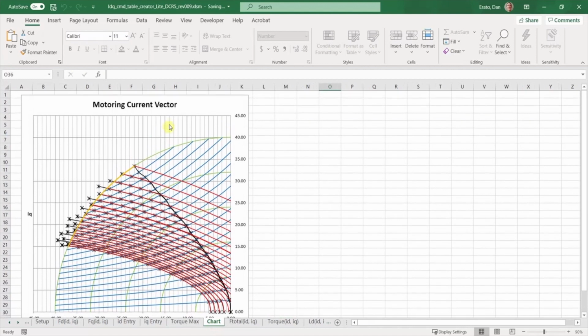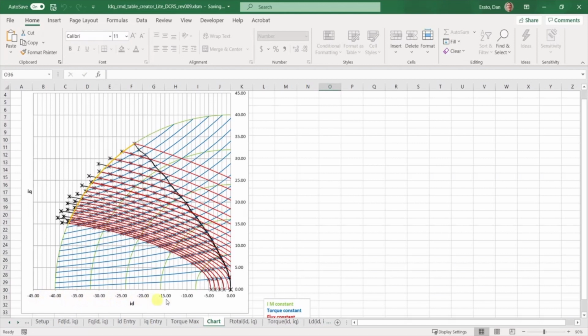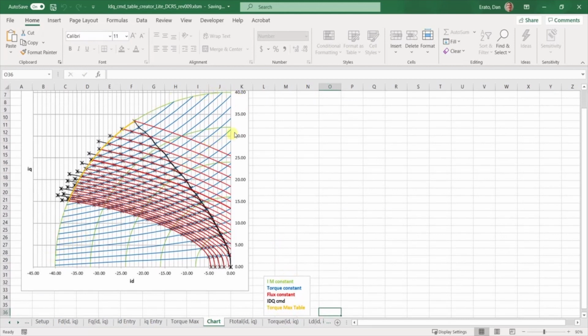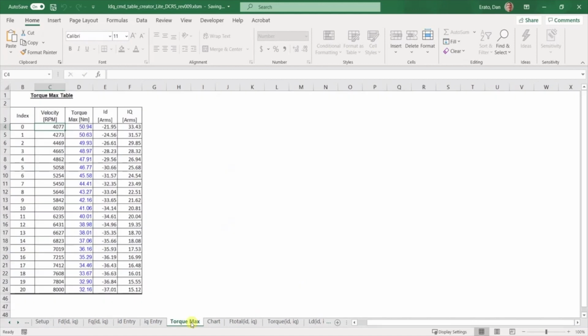The chart sheet graphically shows the IDQ command table with the current, torque, and flux constants. The green lines are the constant current curves. The blue lines are the constant torque curves. The red lines are the constant flux curves and represent the voltage constraints at higher speeds. The black line is the max torque per amp MTPA curve used by the drive below base velocity. At higher speeds, when the drive runs into voltage limits, the IDQ commands follow the flux constant curves. Lastly, the orange line represents the torque max curve shown in the previous sheet.